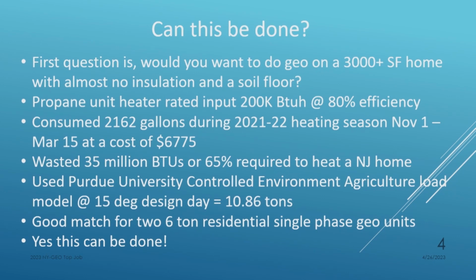So where do you start to do a load calc on this thing? It turns out Purdue University, the agriculture lab, has a model that's available on the web, and we did a load calc. Because they told me they only needed 50 degrees indoors to grow, and at that location the design temperature is 15 degrees, we could do it with 10.86 tons, which said to me two 6-ton residential units.